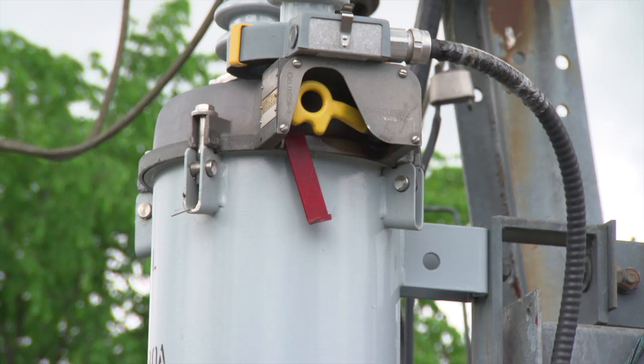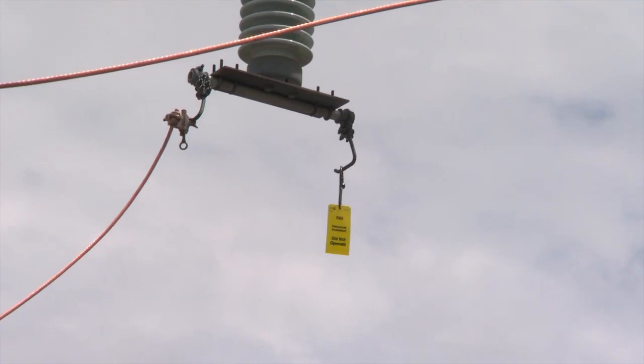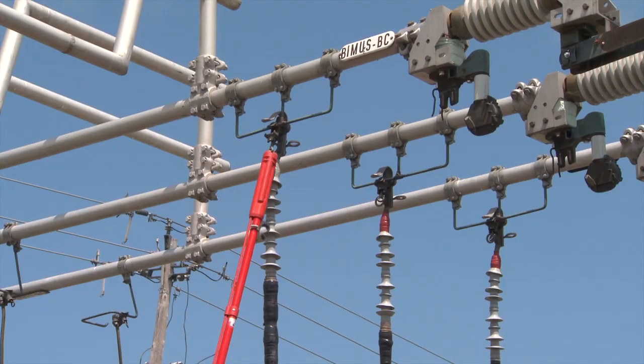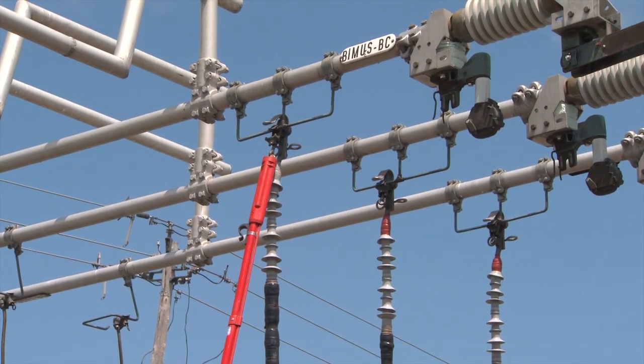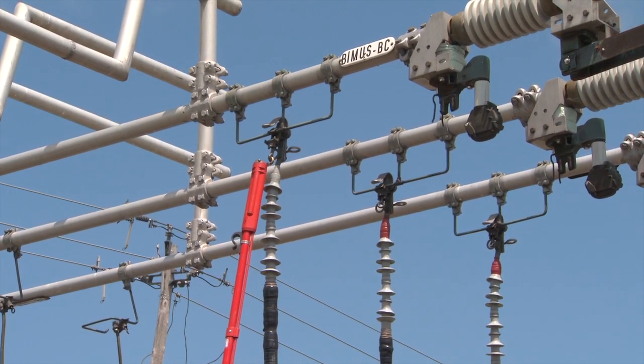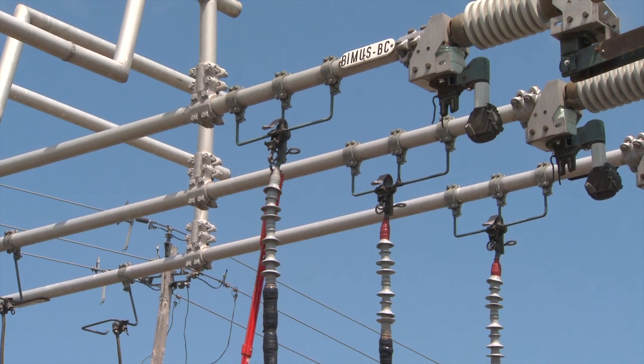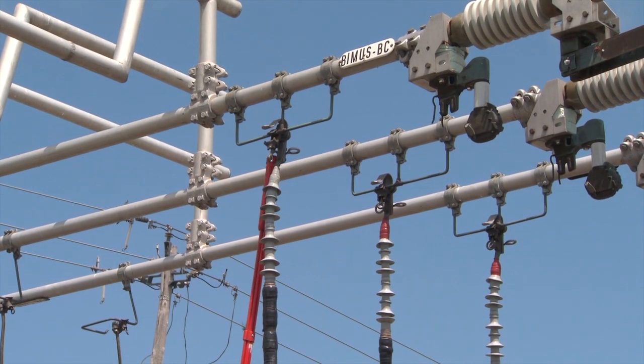Check that the DS reclosers are still in the non-reclosing position. Check that the LC-MUS loops are removed. Prepare and check an OTO to remove the conductors and cables. Remove the MUS low-voltage cables from the DS feeder stirrups.